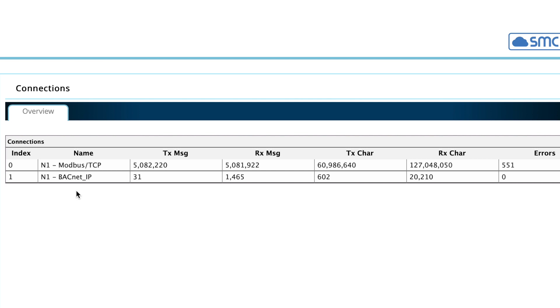Most Protonodes will have two Indexes listed here. Index 0 is normally the protocol used to communicate to the OEM device, and Index 1 will be the protocol used to communicate with the Building Management System.